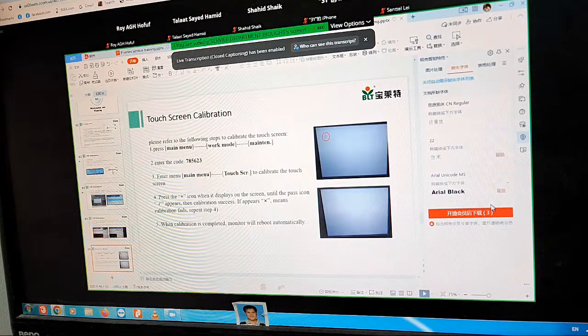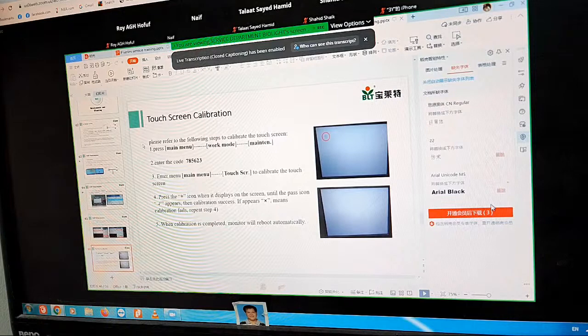Next is about touch screen calibration. Please follow these steps to calibrate the touch screen. First, change the work mode to maintenance and enter the code, the password is 785623. Choose touch screen to calibrate it. You'll see a plus signal, and you need to use your finger or a pen to touch the middle of it, about 4 points. When the calibration is complete, the monitor will show the correct signal and reboot automatically.